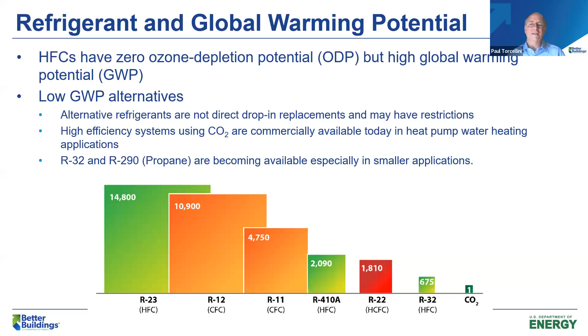But there's a lot of discussion about lower GWP alternatives to what's out there today—things like 410A are especially popular. We're starting to see more equipment with lower global warming potential, such as R32. Some systems, especially for domestic hot water, are looking at carbon dioxide, and propane is also starting to become available, especially in smaller applications. Next slide.